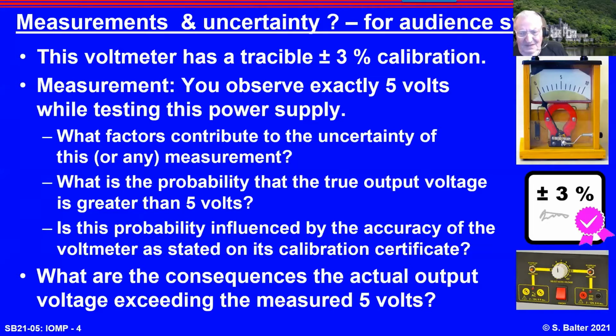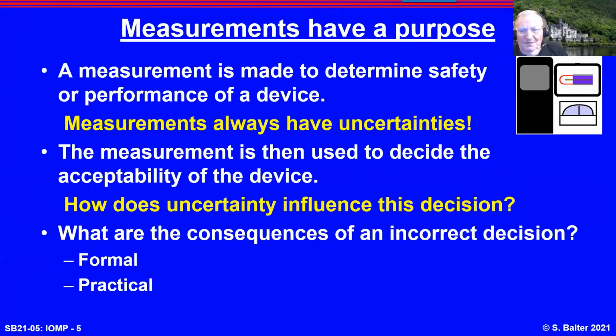And this is pure technology where medical physics judgment is needed. What are the consequences if the actual output voltage exceeds the measured 5 volts? And these are things which each of you, as you do your testing, needs to keep in account. We do measurements to determine the safety or performance of a device. These measurements have uncertainties. You use the measurement to decide the acceptability of the device. The question on the table today is, how does the uncertainty influence the decision? And what are the consequences of an incorrect decision?